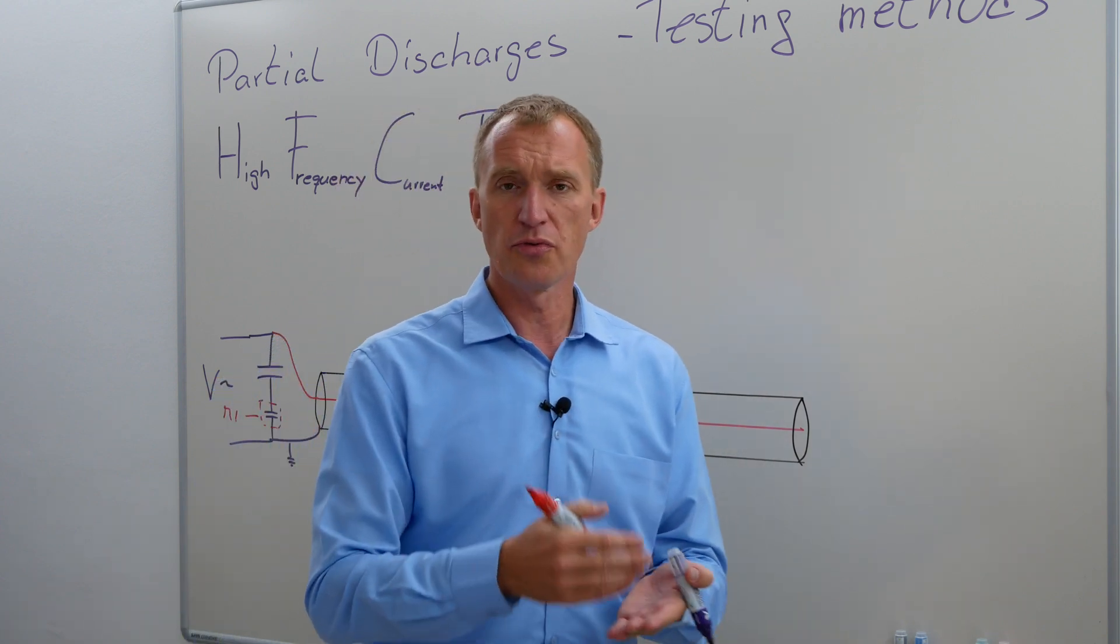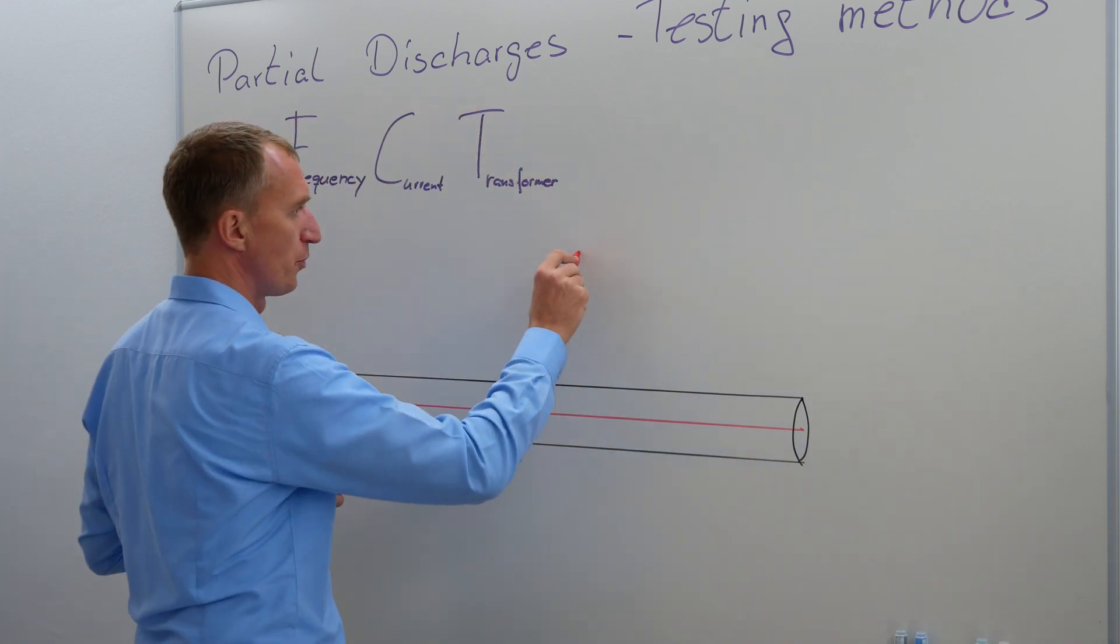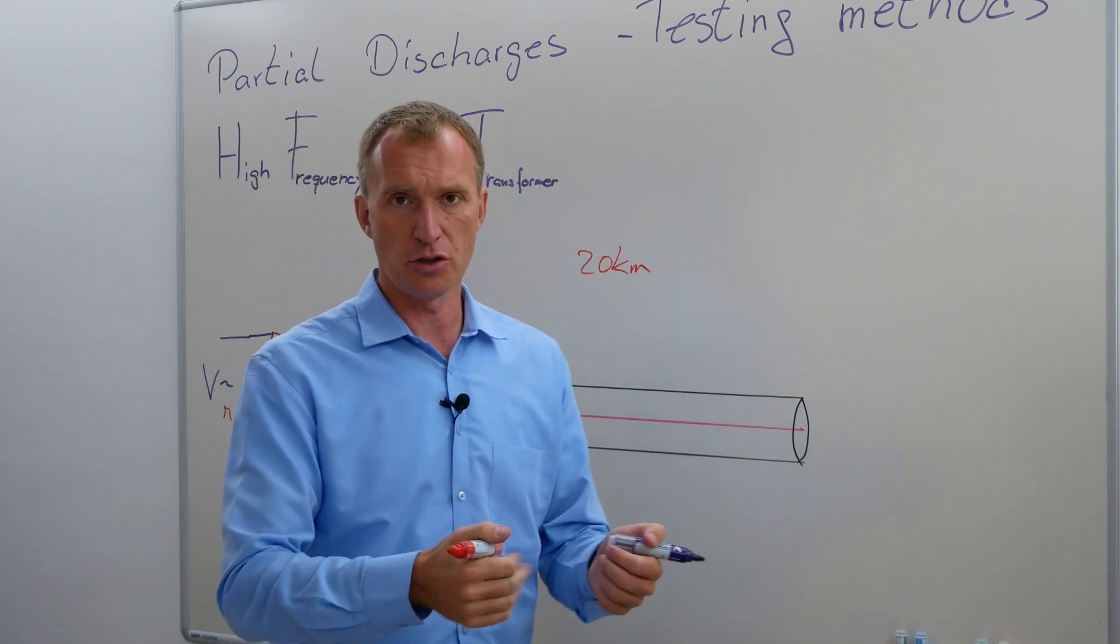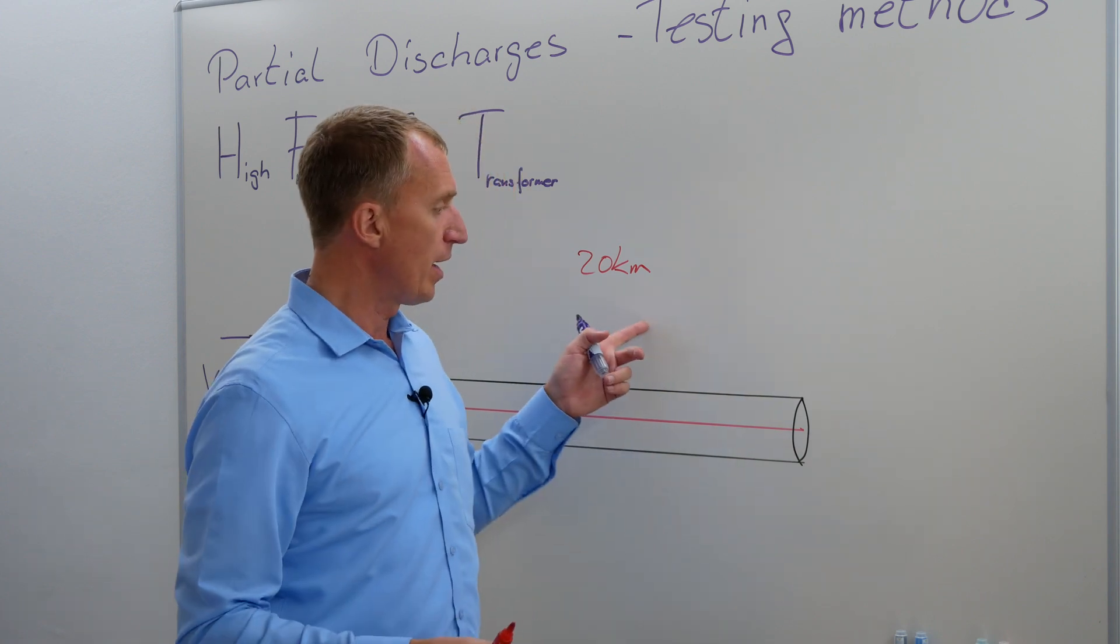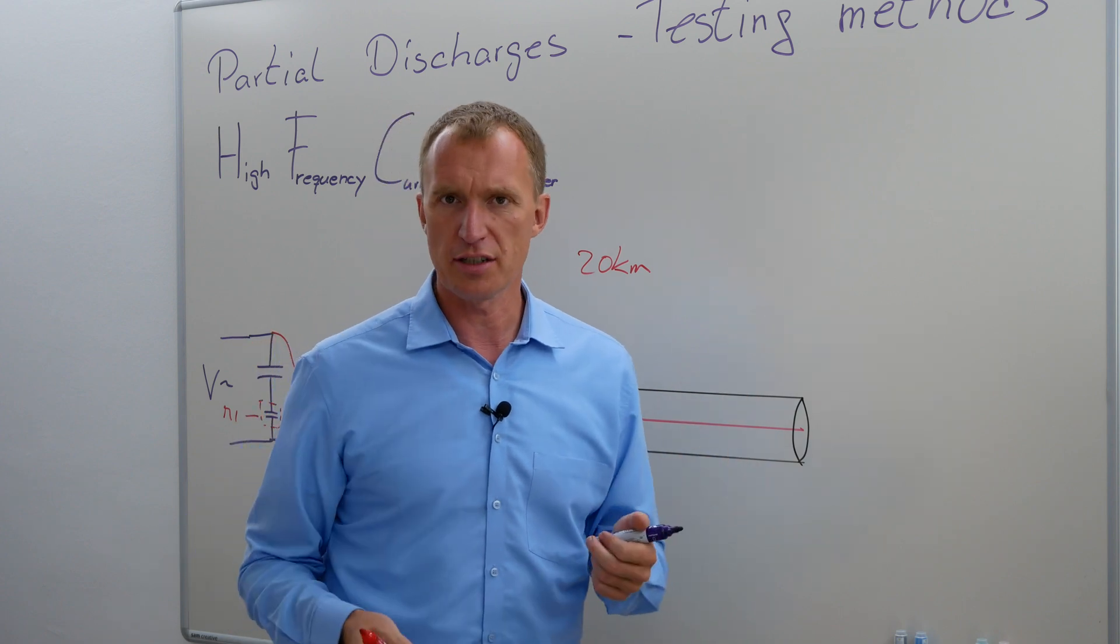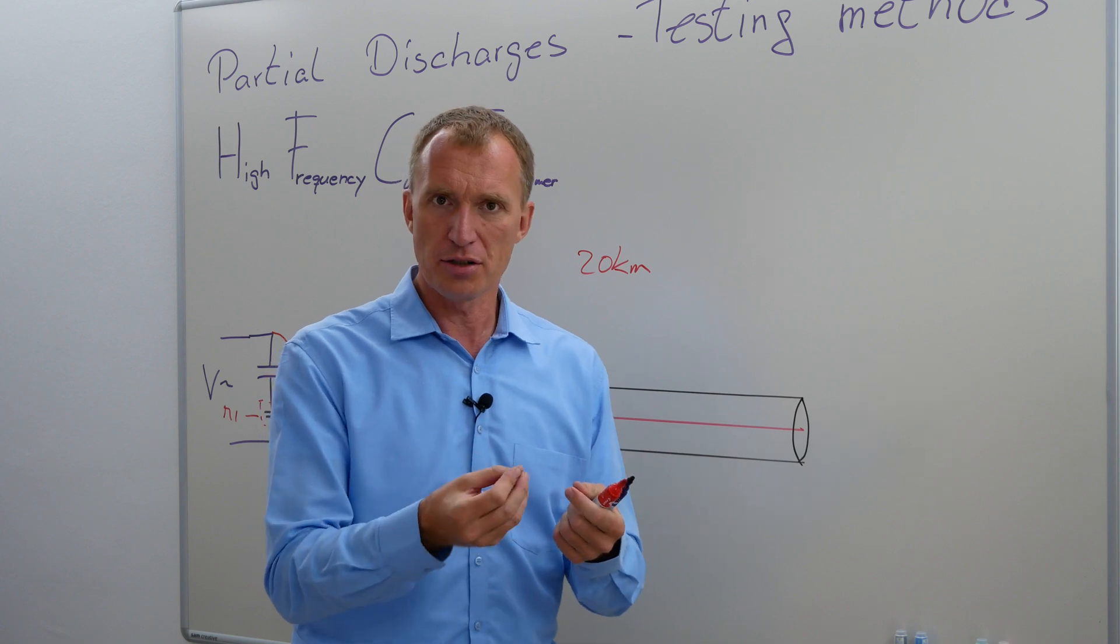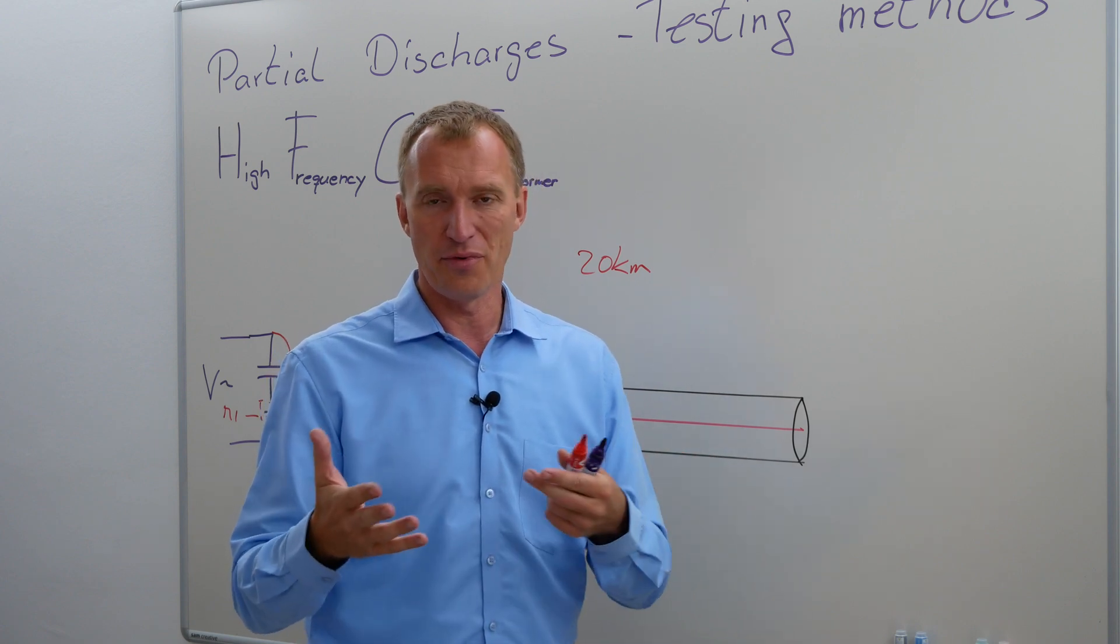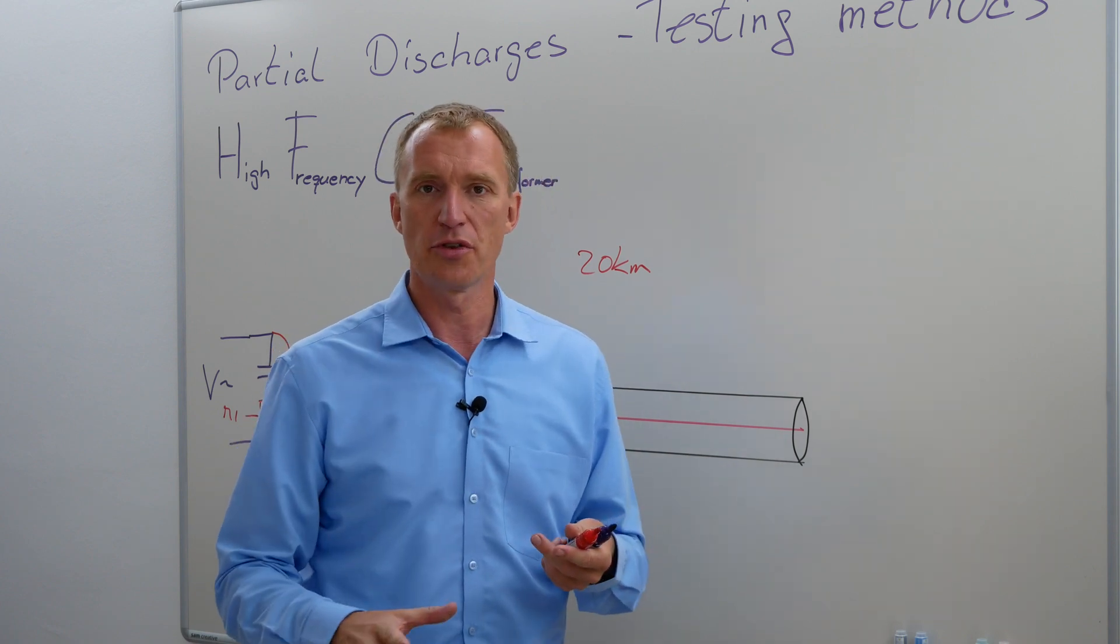So imagine the following thing. You're trying to find partial discharges in a joint. Let's say the cable is 20 kilometers long. I have done that, testing on 20 kilometer long cables, high voltage cables, 400 KV. And in this 20 kilometer cable, we had something like 26 joints or something like that. And you are trying to measure partial discharges which are really, really small, in the area of 10, 5 picocoulomb. Sometimes you would be even happy to see 20 or 30 picocoulombs.